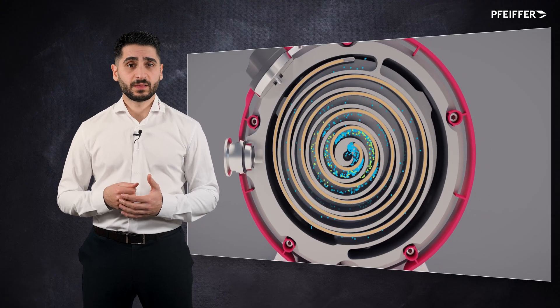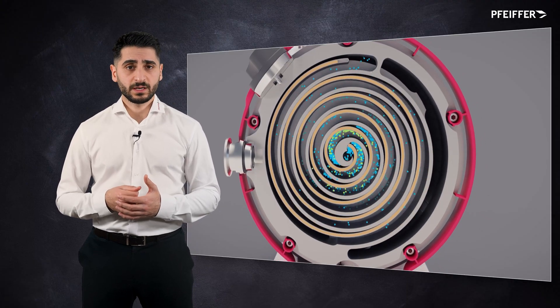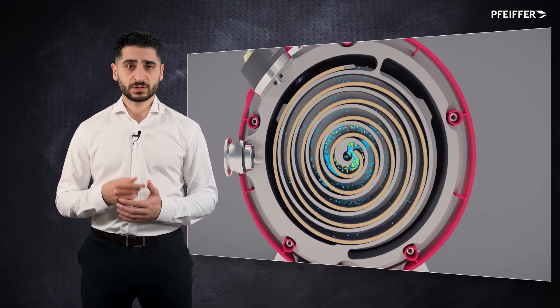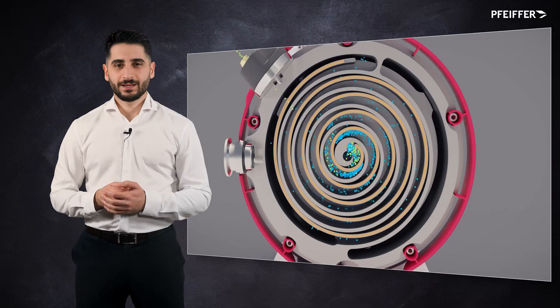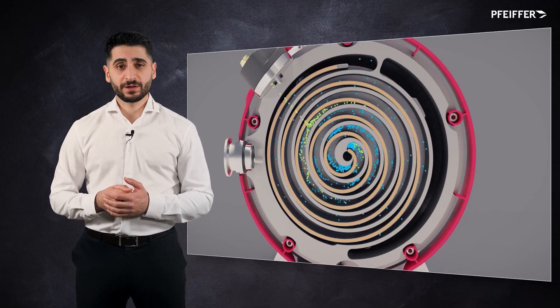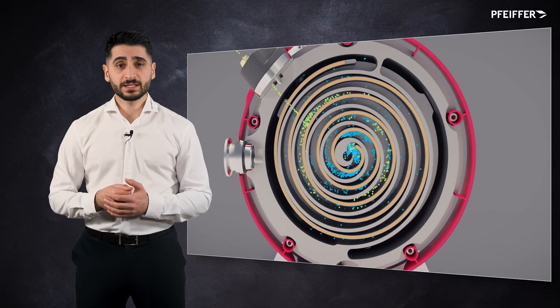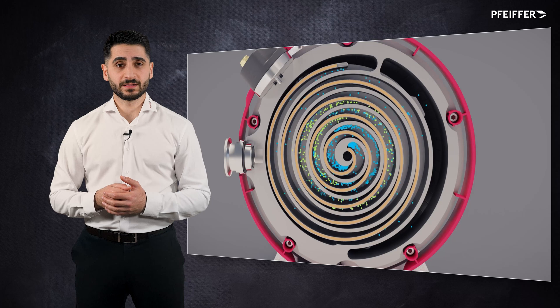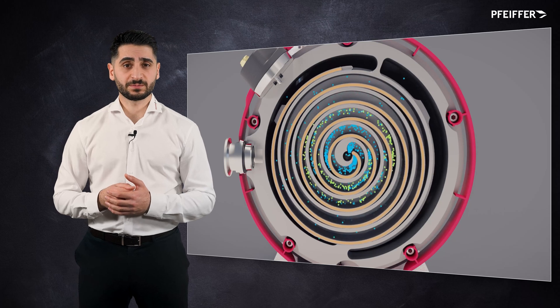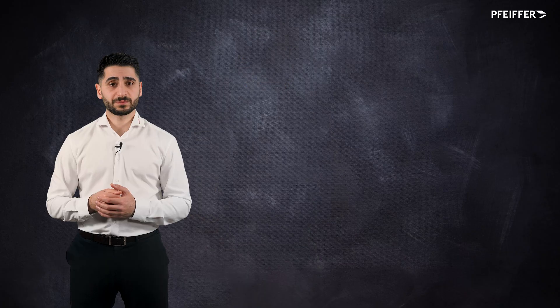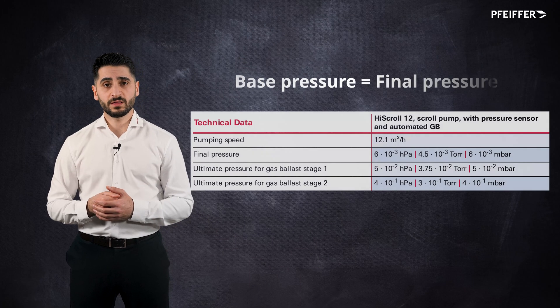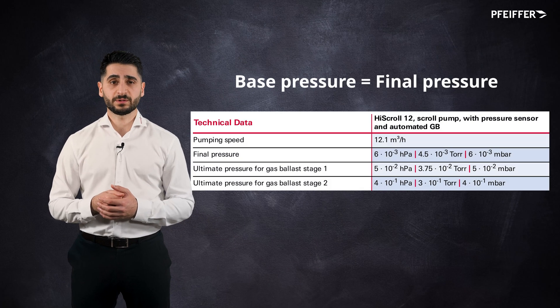inert gas, represented by the yellow dots indicating gas particles, flows into the pump. We can see that the steam is expelled with the ballast gas. This action leads to a slight increase in the achievable base pressure of the vacuum pump. Consequently, vacuum pumps equipped with gas ballast specify the base pressure both with and without gas ballast.